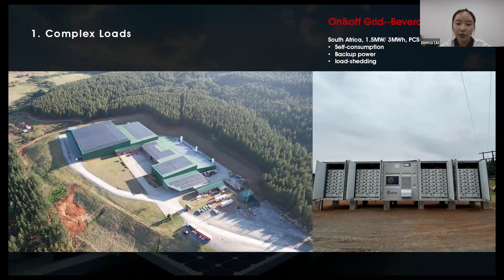It's a local beverage factory equipped with heavy assembly line machines. This project is based in South Africa, and a big factory always comes with complex load types — sensitive loads restarting, causing inrush current, delay response time under heavy load, and harmonics problems. In this case, we must use transformer-based equipment to solve these problems. You can see on the right side the customer installed a rooftop PV system with two sides of ATESS containers — there are 3 transformer-based PCS 500 inverters and 3 megawatt-hours of batteries inside. The system provides uninterrupted and long-lasting power in a cost-effective way. There's no more load shedding issues in this factory from now on.